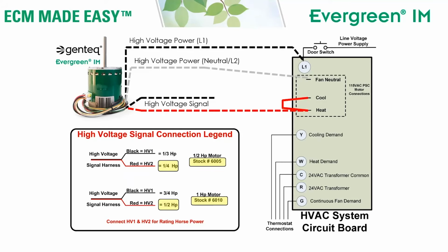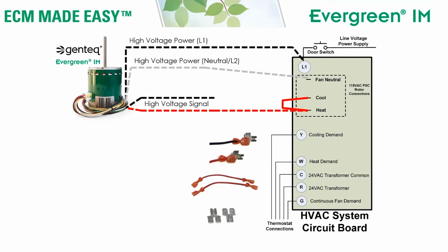If I use only the red wire, my half horsepower motor runs at 1/4 and my 1 horsepower motor runs at 1/2. So with just 1 or 2 wires and a jumper, I've selected the horsepower for the motor, and we're jumpering the heat and cool terminals together so that all demands, heat, cool, or continuous fan, energize the motor at the same horsepower level.